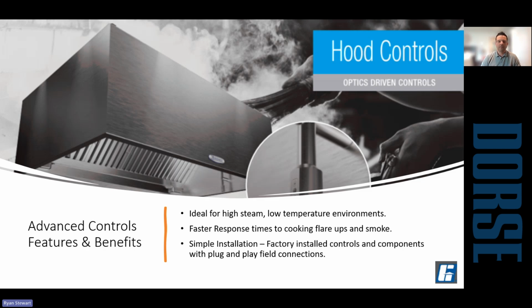The standard DCV handles that by having a 100% override. So the staff would understand, hey, when I put this on here, we're going to have more smoke produced, or I've burned something and there's a bunch of smoke. They can hit the 100% override. It pushes the fans to full speed for 30 minutes, and then it'll look back to the heat sensors in the hood.